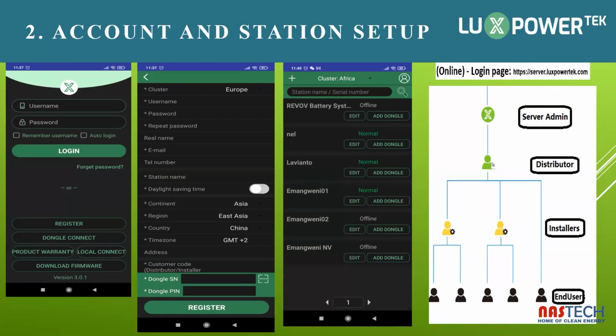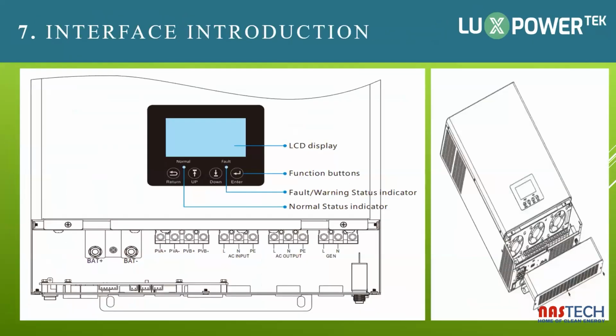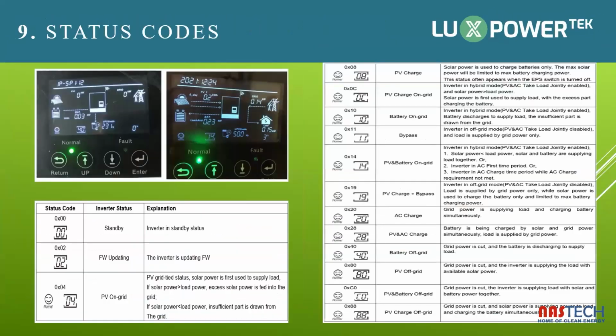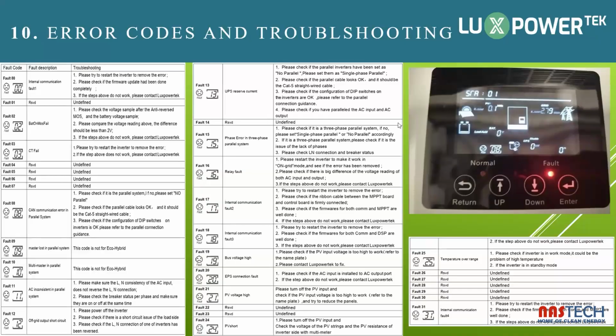Okay. But do any of our customers have any questions? Enrico, I think just to add on to the 2 points that Mr. Kokyo mentioned, especially that fault 17, where there are those benchmarks on the MPPT port. I think you mentioned something about it commonly happening if the panels in the string, the PV voltage, is 500 volts, or is it more than 500 volts? And something about before, if the inverter is not properly programmed to take the PV, maybe you can just elaborate a bit on that if possible.